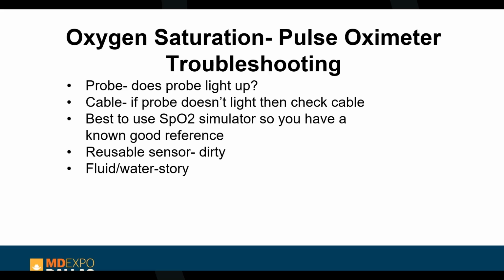So those are big variables with troubleshooting pulse oximetry. Oxygen saturation, pulse oximeter troubleshooting. The probe doesn't light up. That's an easy one to look at. You just look at it and see if it's lit up. If it doesn't light, then check the cable, meaning the trunk cable. There's a short patient cable, and then there's the trunk cable, the longer cable.